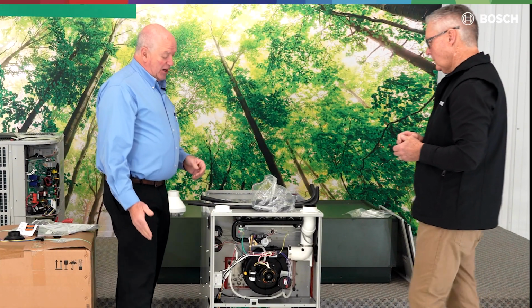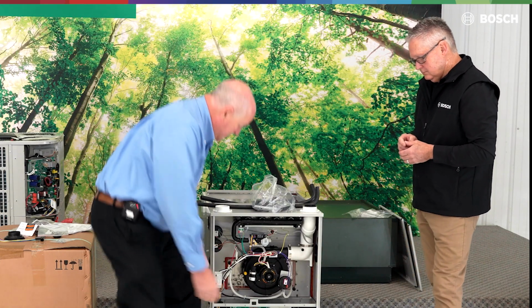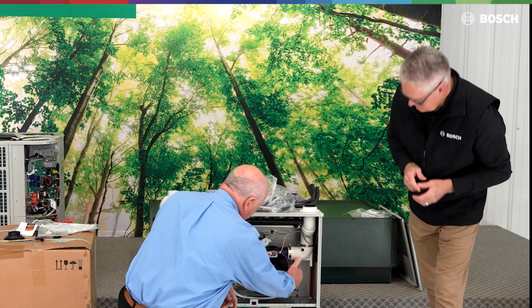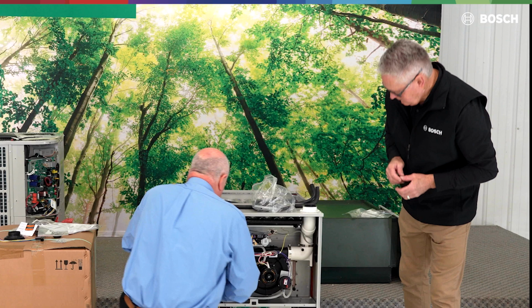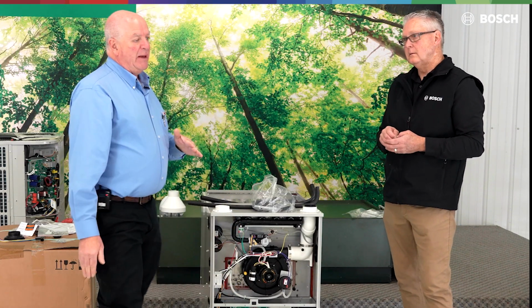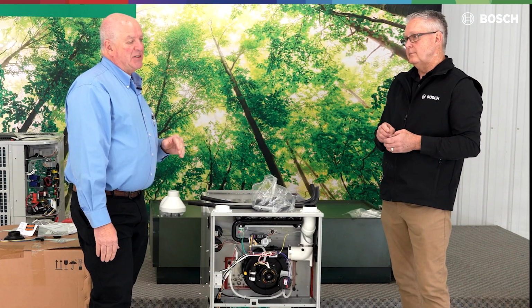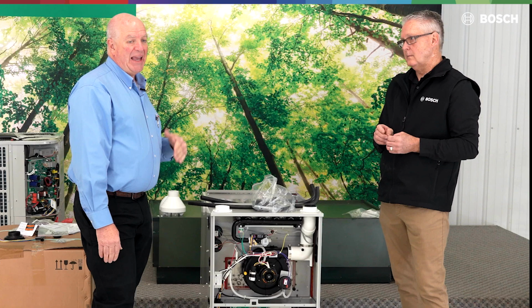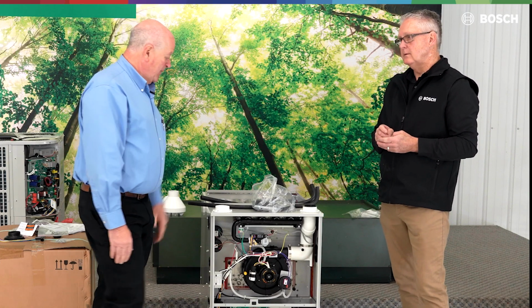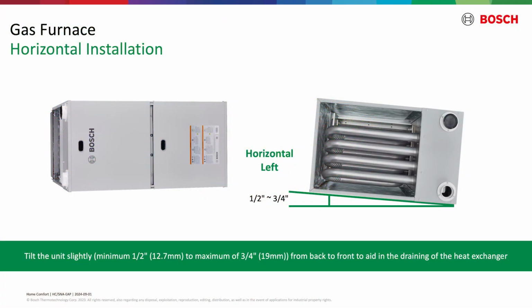Guys and gals, this is our condensate drain in here. This has to flow out of here very easily. This is very acidic water. And our rationale for having a slight slope is that if our acidic water sits in that stainless steel heat exchanger for any length of time, it can eventually eat through it. So we're going to suggest to you a 1/2 inch to 3/4 of an inch of slope, something like that.